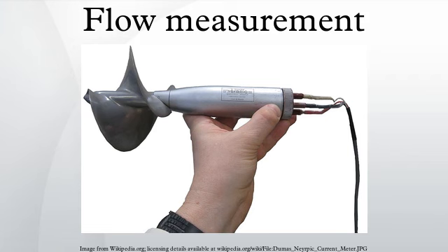By using the absolute transit times, both the averaged fluid velocity and the speed of sound can be calculated. Using the two transit times and the distance between receiving and transmitting transducers and the inclination angle, one can write the equations, where v is the average velocity of the fluid along the sound path and c is the speed of sound. With wide beam illumination transit time, ultrasound can also be used to measure volume flow independent of the cross-sectional area of the vessel or tube. Ultrasonic Doppler flow meters measure the Doppler shift resulting from reflecting an ultrasonic beam off the particulates and flowing fluid.